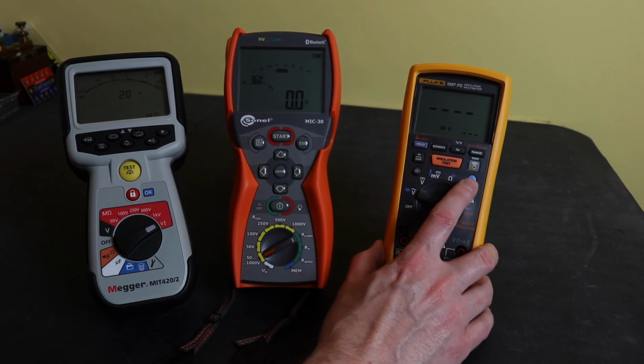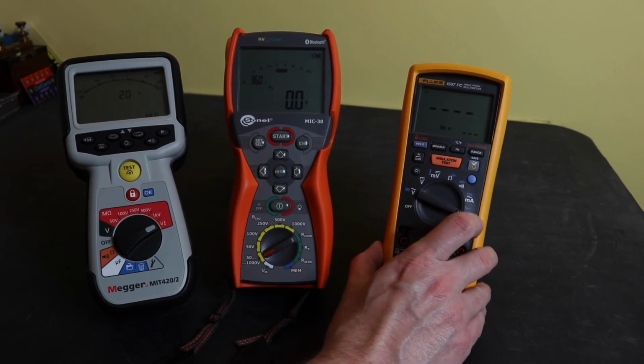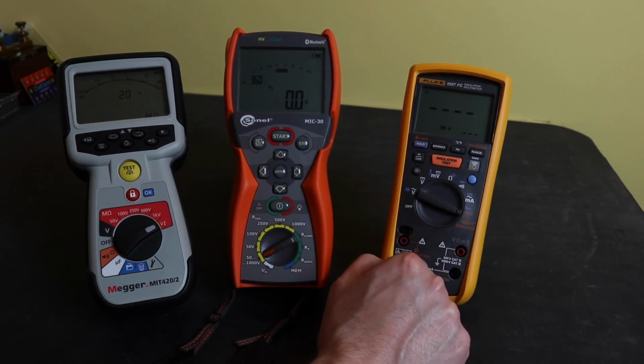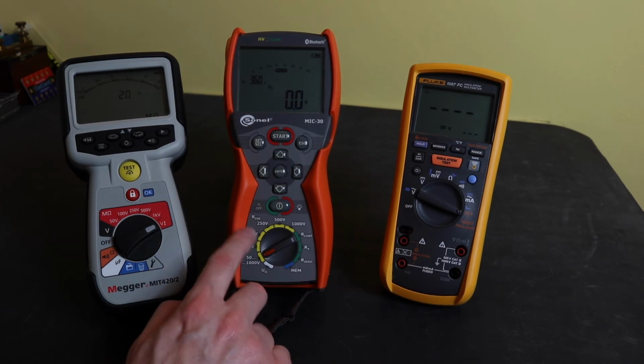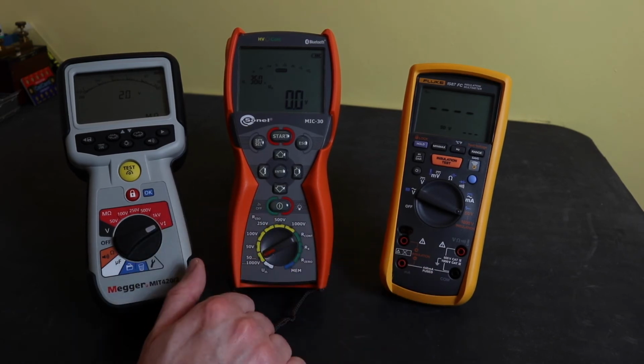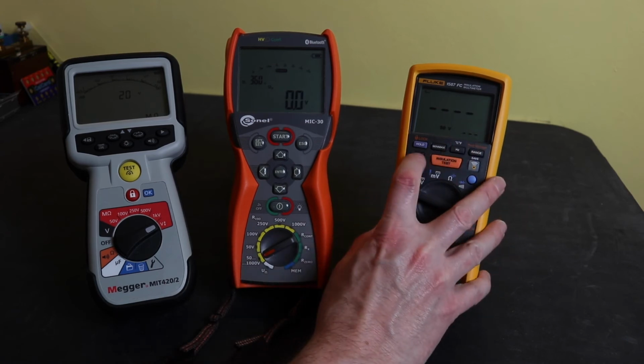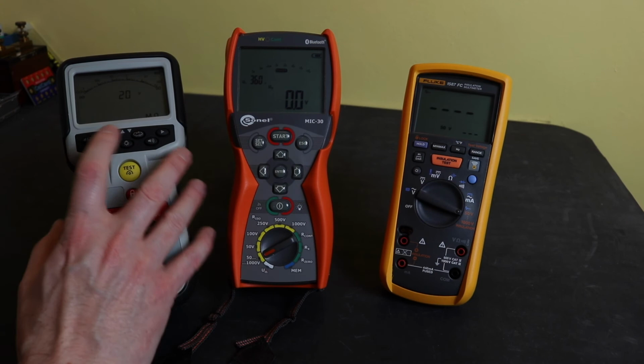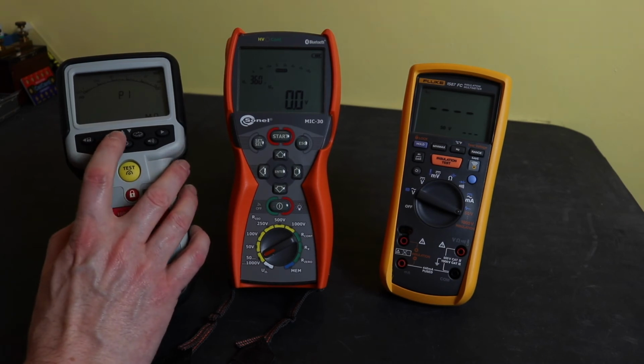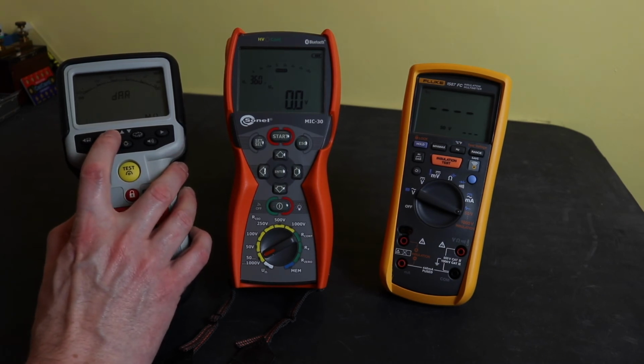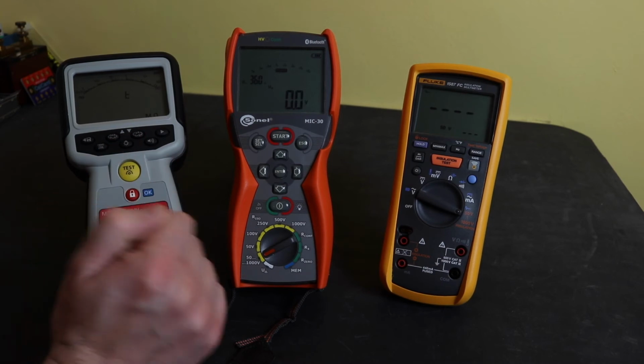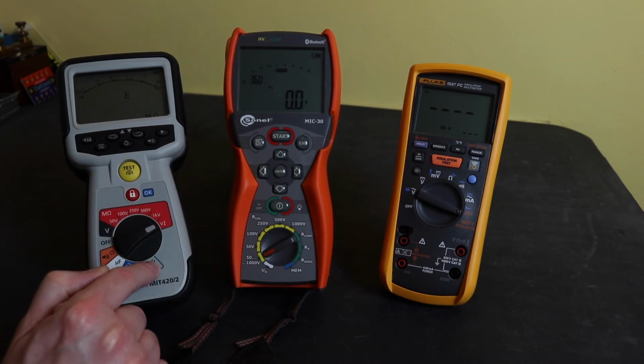However, you do have a smoothing function that you can switch on and off for high resistance measurements. In terms of functionality within the insulation test, all these instruments can do PI and DAR. PI there, DAR there. You can do a PI, DAR, and a timed function there that you set off of the settings function.